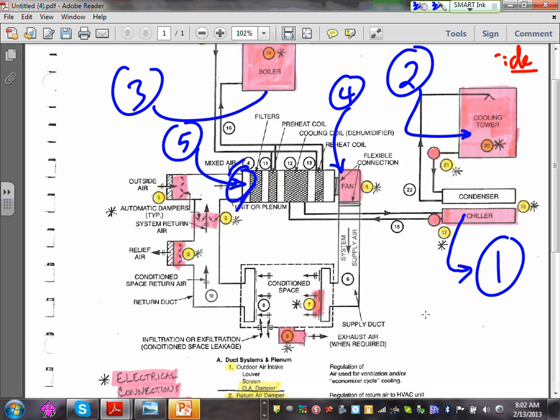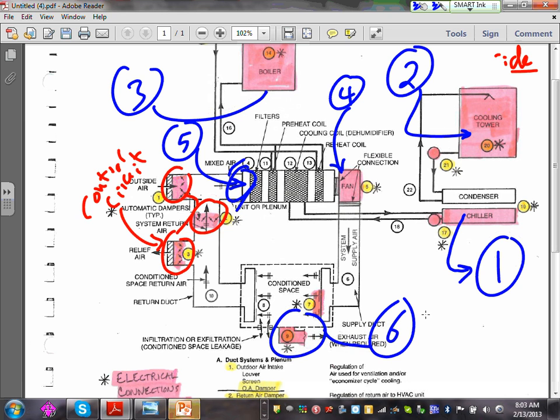Dampers, these dampers, guys, typically they take their circuits from the control. All these dampers have control circuits to open and close them. We have an exhaust fan here. Here's circuit number 5, circuit number 6. All these are required of you as electrical engineer or electrical designer, to provide power to this equipment. The ones that I wrote in red, these guys are dampers, typically powered by the HVAC equipment control system. If they are bigger dampers, we could also provide them with a power circuit.